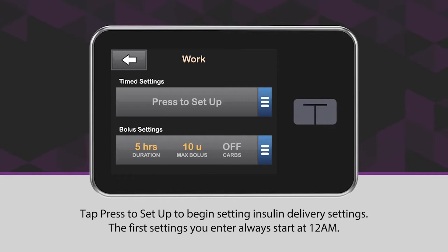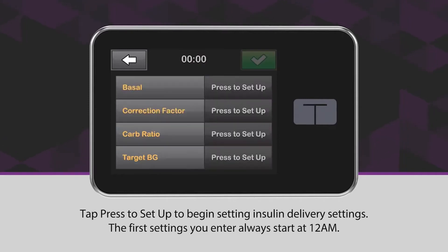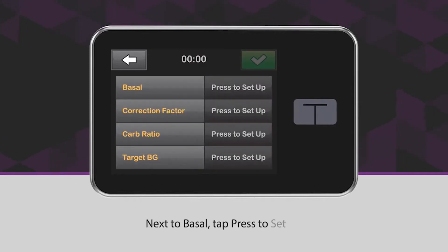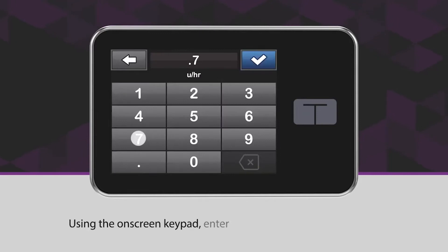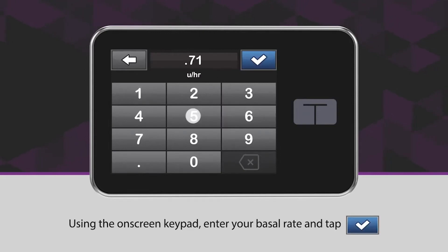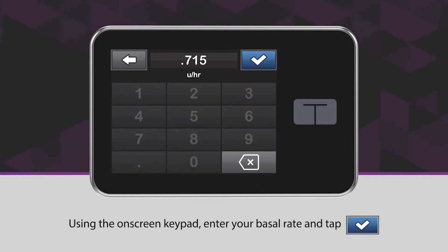The first settings you enter always start at 12 a.m. Next to Basal, tap Press to Set Up. Using the on-screen keypad, enter your basal rate and tap the blue checkmark icon.